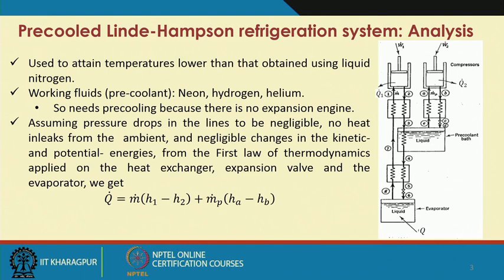This is a modification done to the simple Linde-Hampson in order to achieve a lower temperature than what we can achieve using liquid nitrogen. Here the working fluids are neon, hydrogen, and helium, which are what we call the pre-coolant. The pre-coolant is pre-cooling the actual process fluid. This pre-cooling is done because we are not using any expansion engine — had we been using an expansion engine, we would not have needed this kind of pre-cooling.